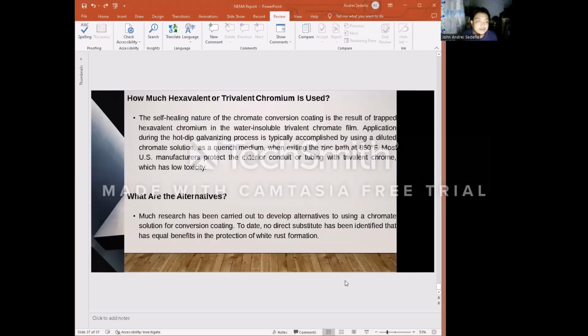And last is how much hexavalent or trivalent chromium is used. The self-healing nature of chromate conversion coating is a result of trapped hexavalent chromium in the water insoluble trivalent chromate film. Application during the hot dip galvanizing process is typically accomplished by using a dilute chromate solution as a quench medium when exiting the zinc bath at 850 Fahrenheit. Most US manufacturers protect the exterior of conduit tubing with trivalent chrome, which has a low toxicity.